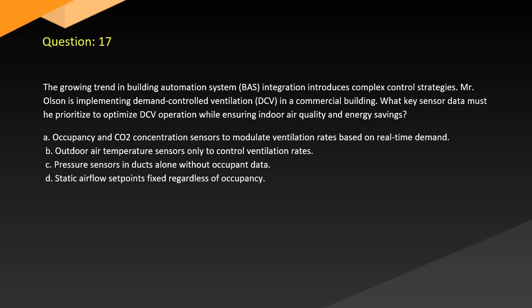Question 17. The growing trend in building automation system, BAS, integration introduces complex control strategies. Mr. Olson is implementing demand-controlled ventilation, DCV, in a commercial building. What key sensor data must he prioritize to optimize DCV operation while ensuring indoor air quality and energy savings? A. Occupancy and CO2 concentration sensors to modulate ventilation rates based on real-time demand. B. Outdoor air temperature sensors only to control ventilation rates. C. Pressure sensors in ducts alone, without occupant data. D. Static airflow set points fixed regardless of occupancy.